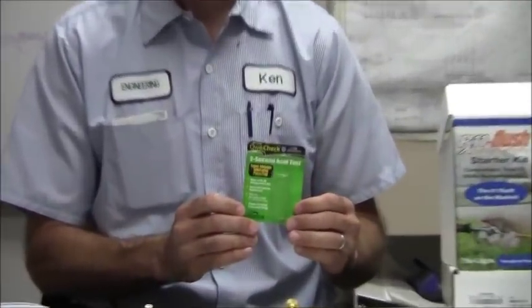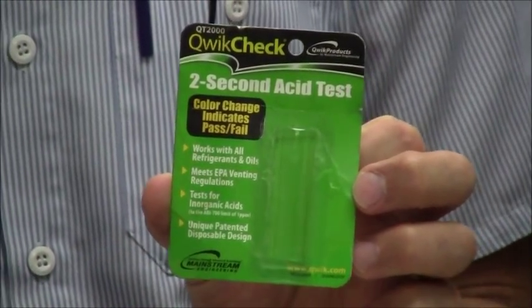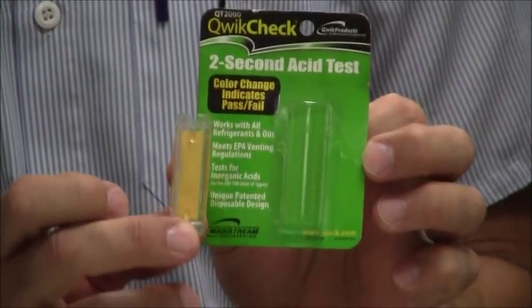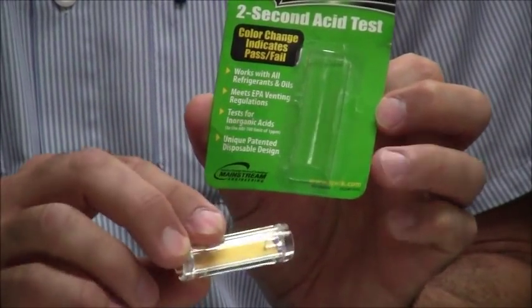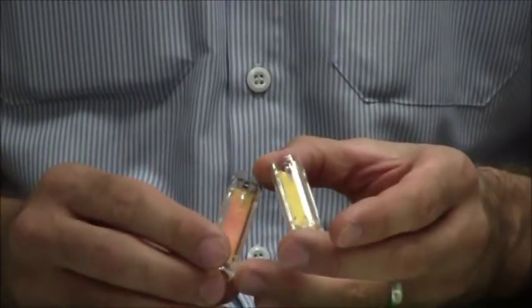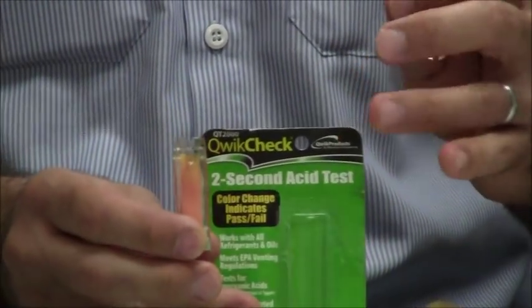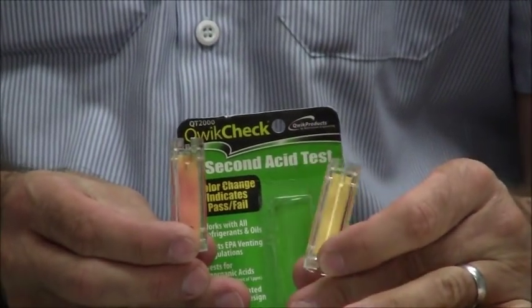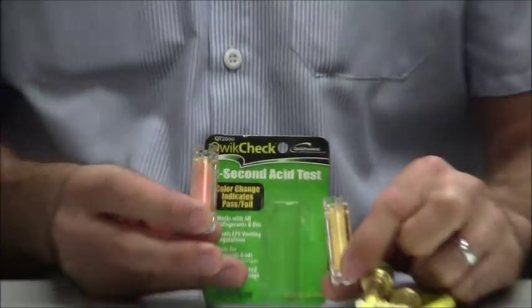So you need to test the refrigerant. The way we tested it was with this kit called QwikCheck. You just put it onto the Schrader valve for two seconds to allow it to flow. If it changes color like this, you know that you have acid in your system because this is an acid test. This is what they look like new, and this one is from our system — so we know that we have acid in the system.